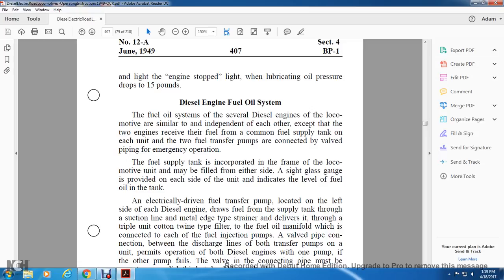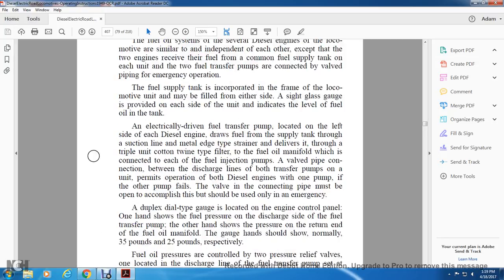Diesel engine fuel oil system. The fuel oil systems for the several diesel engine locomotives are similar and independent of each other, except that two engines receive their fuel from a common fuel supply tank on each unit. The two fuel transfer pumps are connected with a valve for emergency operation. The fuel supply tank is incorporated with the frame of the locomotive unit and may be filled from either side. A sight glass gauge is provided on each side of the unit and indicates the level of fuel oil in the tank.